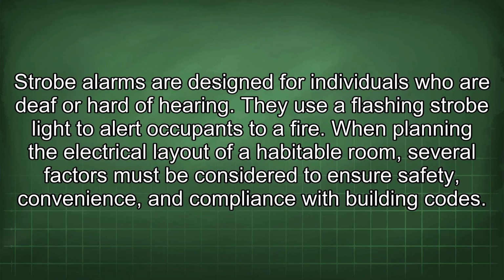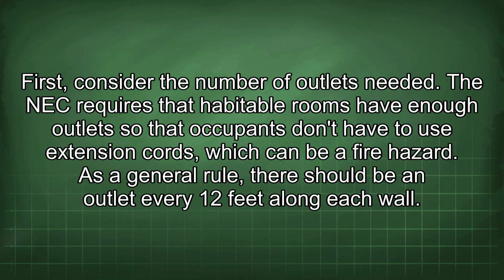They use a flashing strobe light to alert occupants to a fire. When planning the electrical layout of a habitable room, several factors must be considered to ensure safety, convenience, and compliance with building codes. First, consider the number of outlets needed. The NEC requires that habitable rooms have enough outlets so that occupants don't have to use extension cords, which can be a fire hazard. As a general rule, there should be an outlet every 12 feet along each wall.